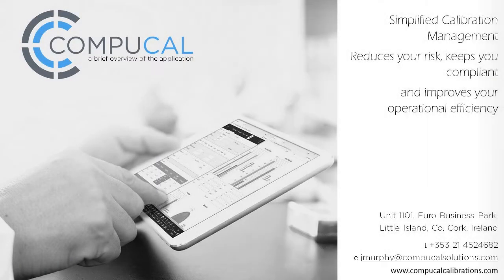CompuCal is a web-based calibration management solution hosted on a secure cloud environment. It is a fully validated software, compliant with FDA 21 CFR Part 11 regulations. The application can be accessed by authorized users from anywhere, using an internet browser. The license of the application determines how many users can access the system at the same time.